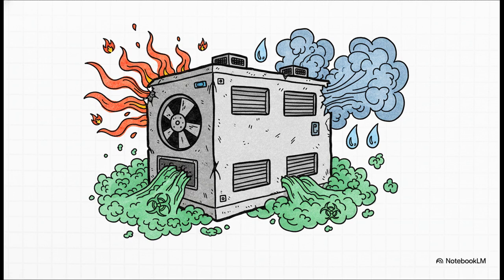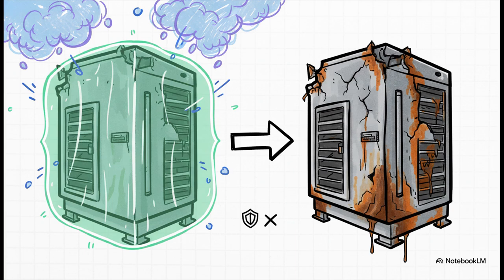This hot, wet, chemical-heavy air means the exhaust side of the unit is just incredibly vulnerable. Throw a standard metal casing in there? Yeah, no way. It simply isn't going to survive. Since a swimming pool is officially a C4 corrosivity environment, you have to match your materials to that exact threat level. To actually guarantee that 15 to 20-year lifespan you expect from a heavy-duty air handling unit, you absolutely need to use a high-durability paint system on any steel or aluminum casing. You've got to specify a system built for C4 right from the jump. Because if you don't, both the internal components and the casing itself are going to degrade incredibly fast, leading straight back to those catastrophic failures we talked about at the very beginning of the explainer.